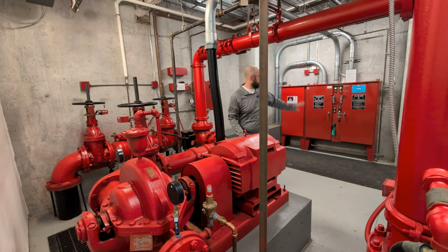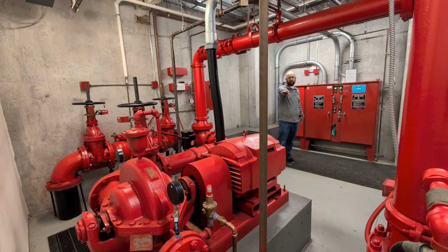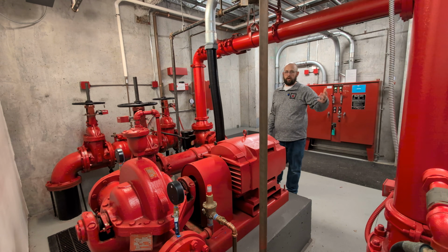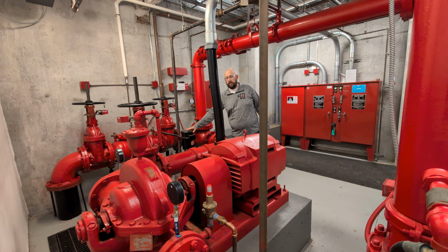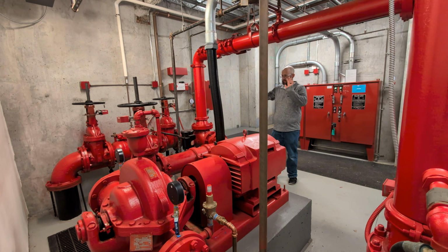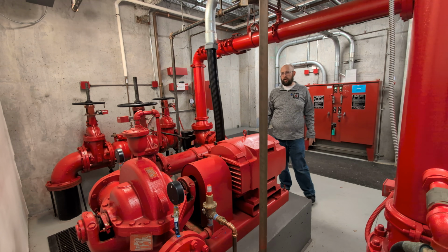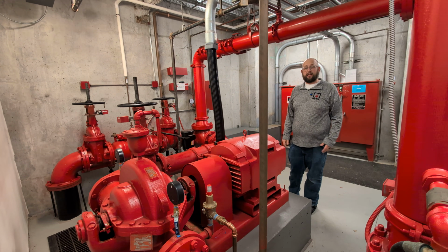I said part of the assembly is the controller. This controls the motor, which runs that pump. So this is monitoring the pressure in the system. Once we hit a specified pressure drop, it'll kick on the motor, which will turn that pump. To keep this from turning on and off if we have small leaks in our system, we have a pressure maintenance pump over here. This is a much smaller pump, which kicks on and off just to make up for any small pressure drops. And we've got a pump controller over here just controlling that pressure maintenance pump, or jockey pump, as some call it, that would maintain that pressure. So this has a sensing line that goes over to our system and is monitoring that system pressure. So basically I have two pumps, a lot smaller one, which is maintaining all of that pressure. So that all being said, let's get into some of our questions.